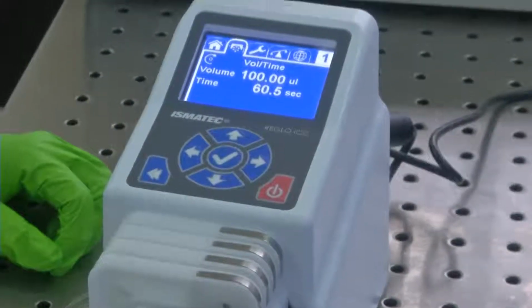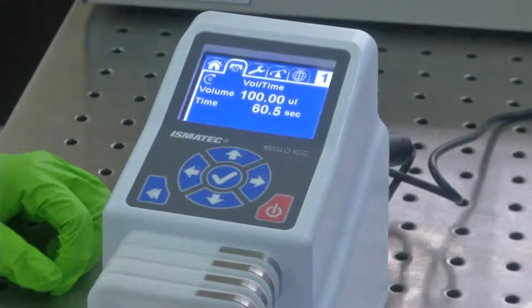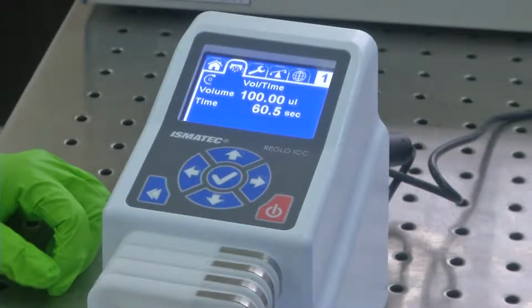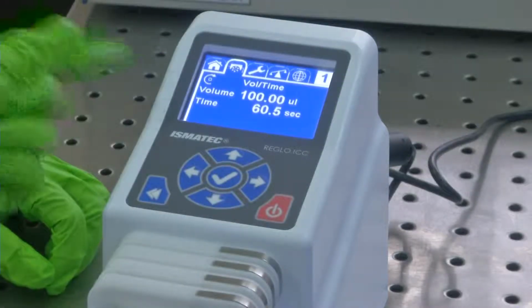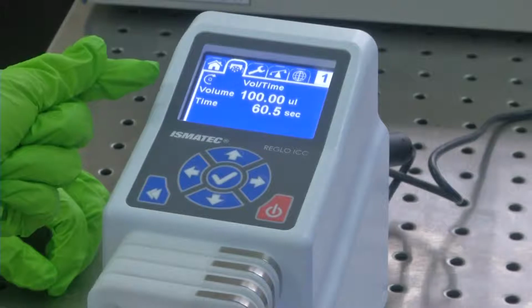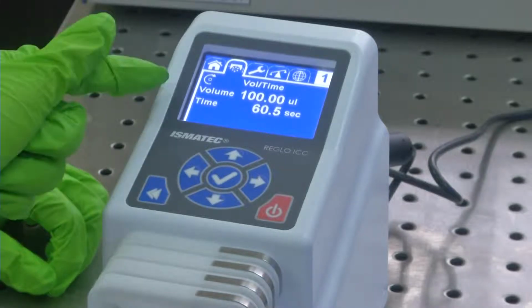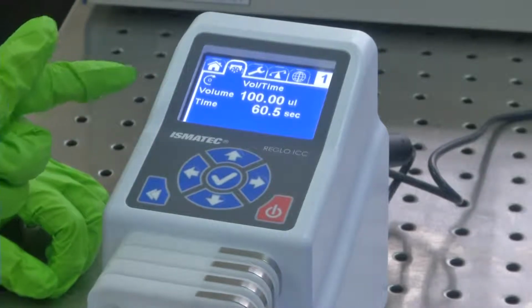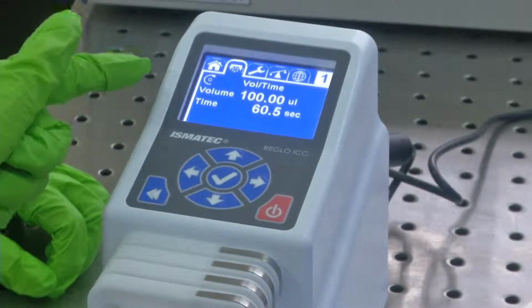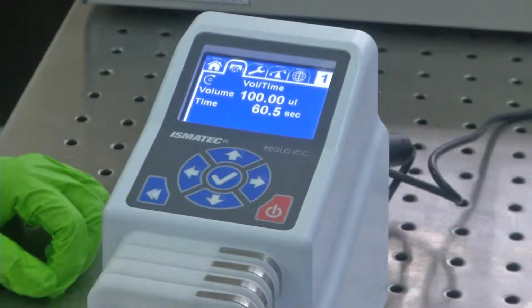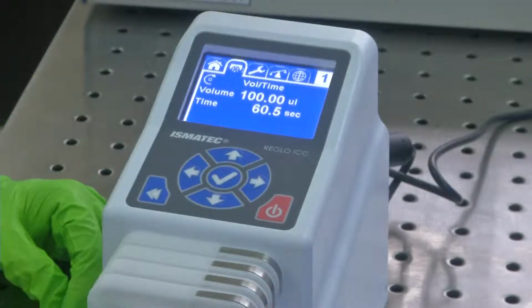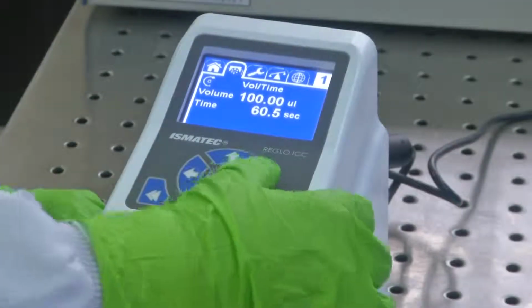So this is telling, say, the symbol on the left side is rotating clockwise. So the first cassette would rotate in the clockwise direction, and what is the volume of fluid it draws? It is 100 microliter per second. So 100 microliter per second of fluid will be drawn through this tubing. This is the configuration of the first cassette, which is this one. So what are the other options available?